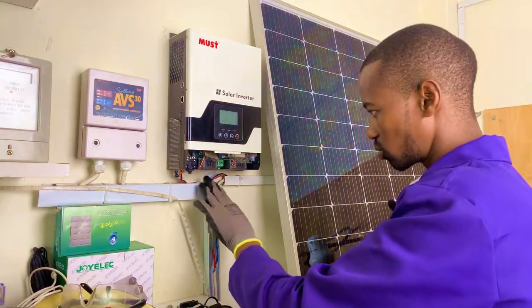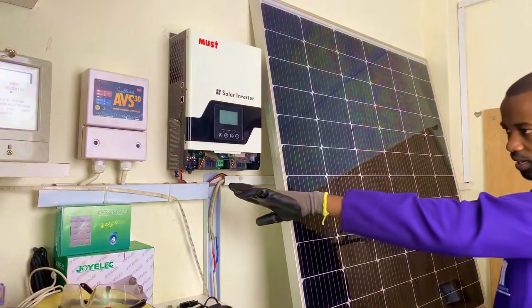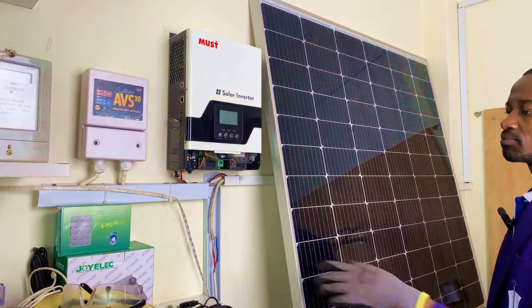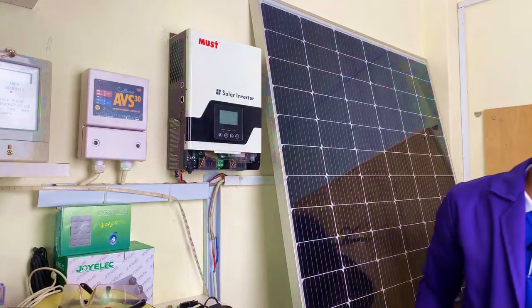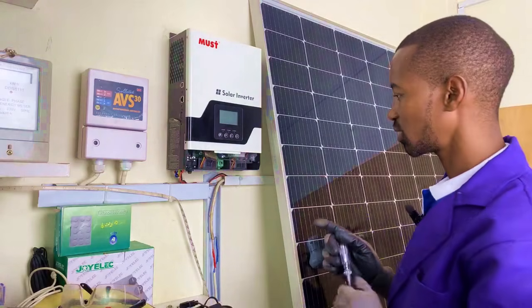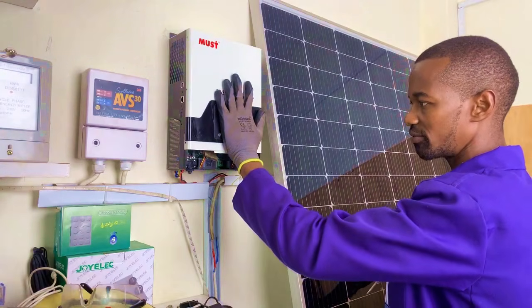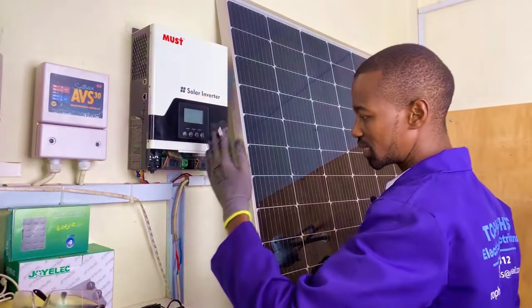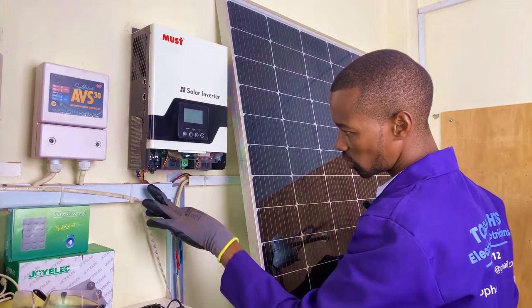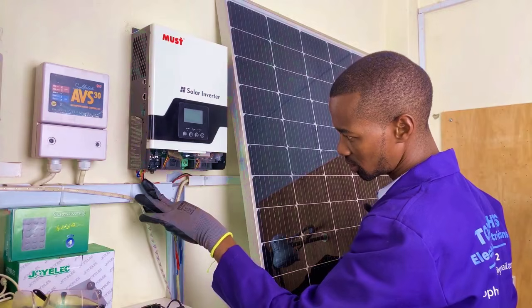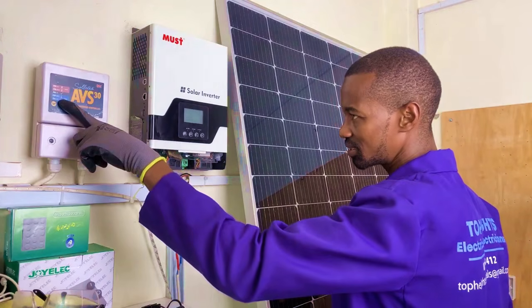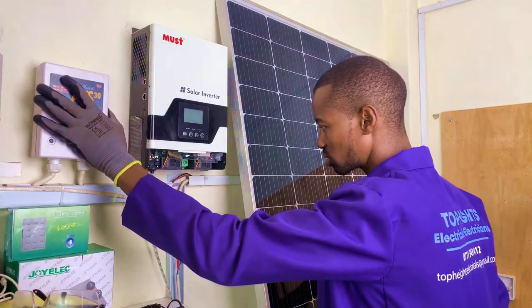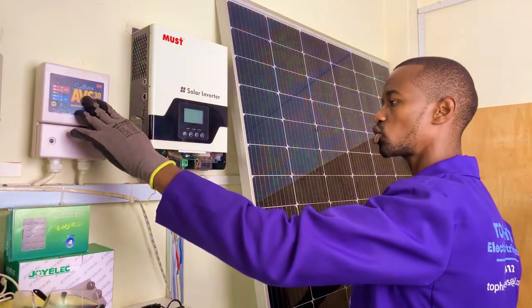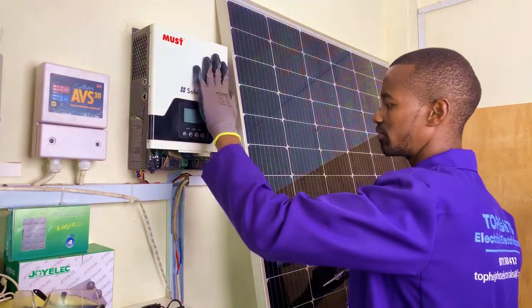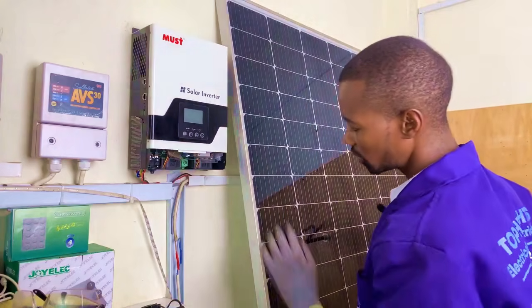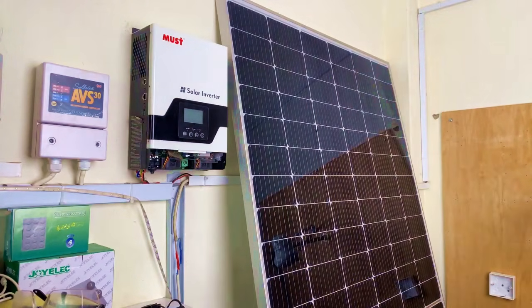You cannot feed the inverter in the absence of a battery, because there would be excess currents coming all the way to the inverter, which might damage it. So the battery is the next connection after you have connected the load and the AC. Still the AC is absent from this connection - if someone were to switch on AC accidentally, our inverter is damaged. Now, before we connect the PV, we then connect our battery.